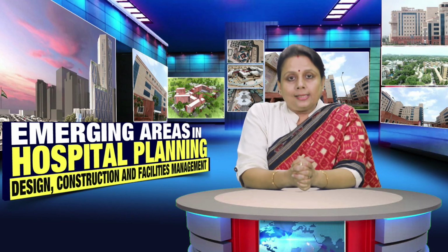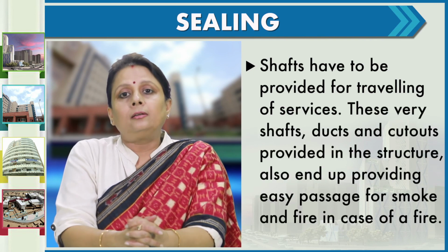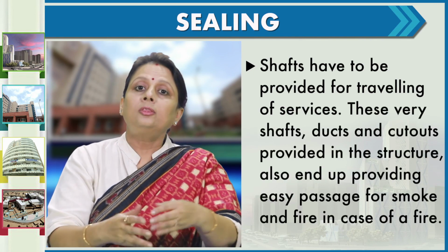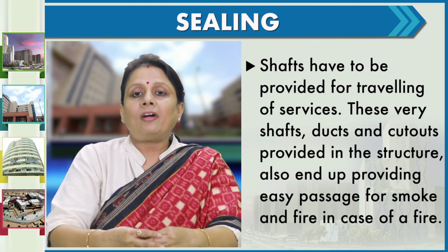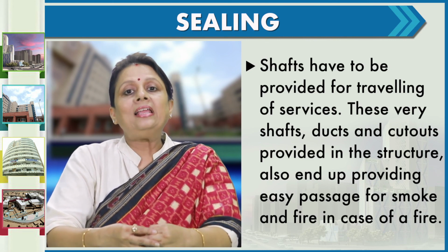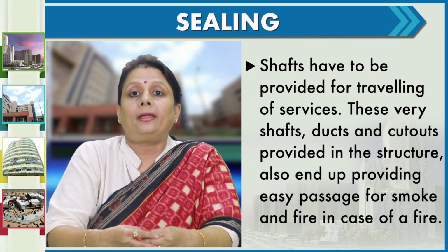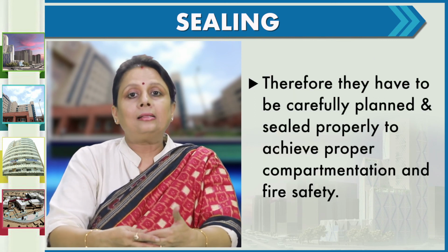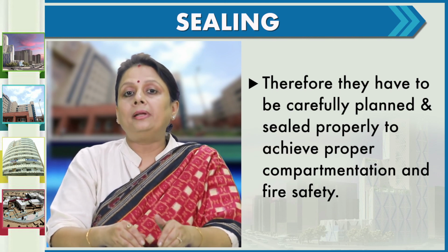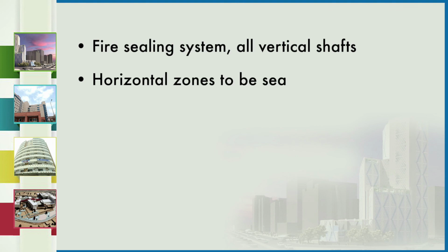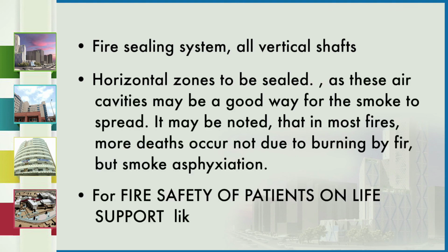Now we have to also seal the shafts. Shafts have to be provided for travelling of services. Now these very shafts, ducts and cutouts provided in the structure also end up providing easy passage for smoke and fire in case of a fire. Therefore, they have to be carefully planned and sealed properly to achieve proper compartmentation and fire safety. The sealing system of all vertical shafts, horizontal shafts, etc. has to be there, as these air cavities may be a good way for the smoke to travel. It may be noted that in most fires, more deaths occur not due to burning by fire, but smoke asphyxiation.